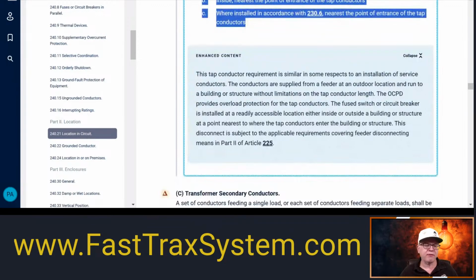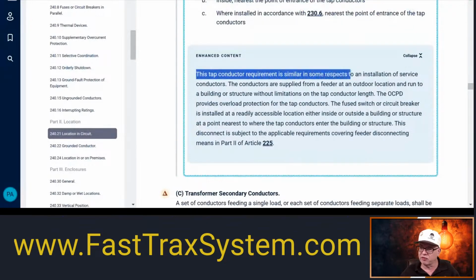And then there's a good informational note, a good commentary. I've got to be careful with that. It is an informational note in the code, and it is commentary. And of course, informational notes are not enforceable. This is just commentary from whoever wrote the handbook, because this is probably the same info that's in the handbook. Basically, it's just saying the tap conductor requirement is similar in some respects to the installation of service conductors. That is true. Outside, nearest point of entry.